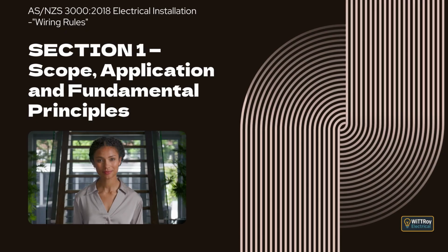Clause 1.5.11.3, Voltage disturbances and electromagnetic influences. This clause states that protection against damage from overvoltage caused by events such as lightning, or caused by switching operations, is not a requirement of this standard. However, it points readers to guidance in Clause 2.7 in Appendix F, which explains how to manage surge protection if it is needed. Even though surge protection is not mandatory here, it may still be required in other standards or for sensitive equipment.